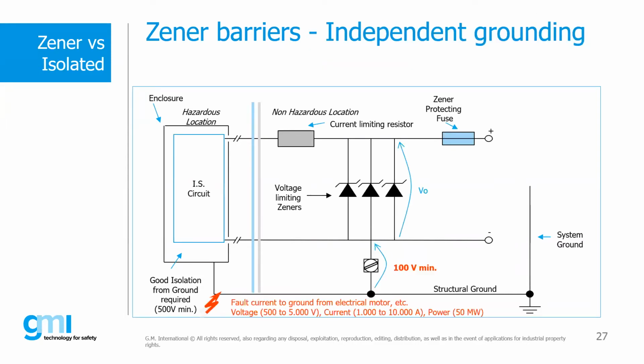So again, independent grounding is a potential fault condition. This is where we really want to pay attention. That's the important thing to take away from this webinar today. I don't want to tell you not to use Zener barriers, but let me say this: GMI does not manufacture Zener barriers. GMI only makes isolated barriers, and I believe in isolated barriers myself. I think they're much safer, much more robust, and it's a better system, with fewer things that can potentially go wrong. However, if you do use Zener barriers, the important thing to remember is to pay particularly close attention to the potential fault conditions that we can see when using Zener diode type barriers.